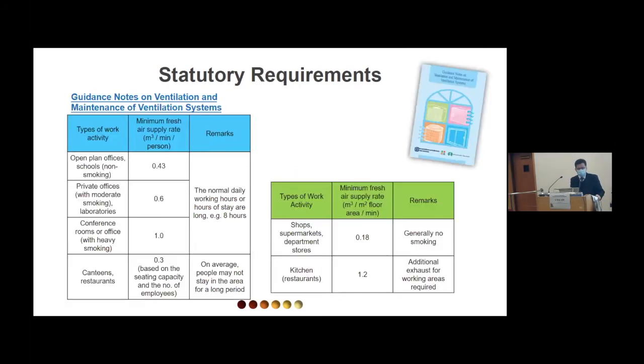The guidance notes on ventilation and maintenance of ventilation systems issued by the Labour Department also specify the fresh air supply rate for general work activities in air-conditioned areas. For places such as offices, schools, conference rooms and canteens, where the number of persons present is normally constant or nearly constant, a minimum fresh air supply rate in terms of the number of persons is specified. But for places such as shops, supermarkets and restaurants, where the number of persons may vary from time to time, the minimum fresh air supply rate in terms of the total floor area of that workspace is specified instead.